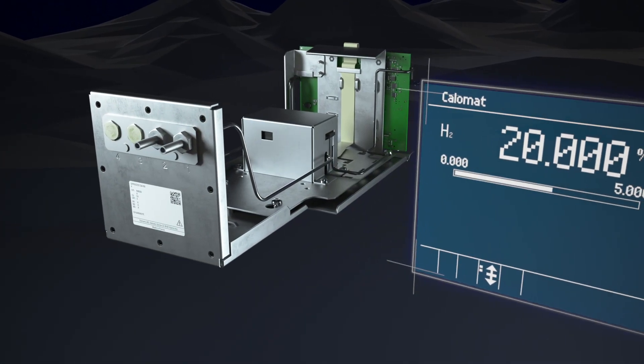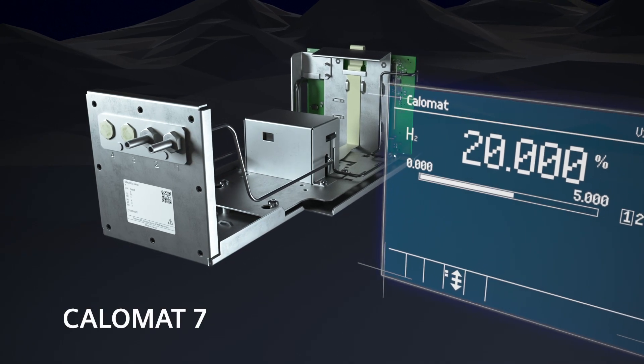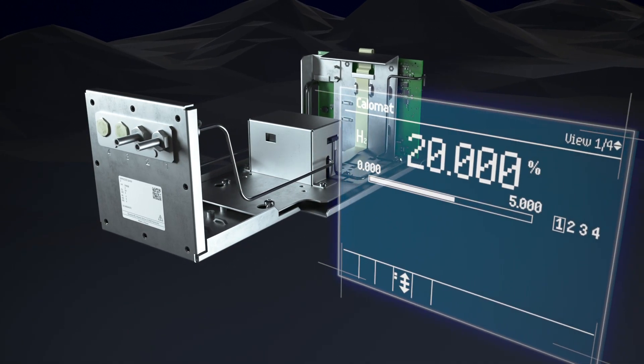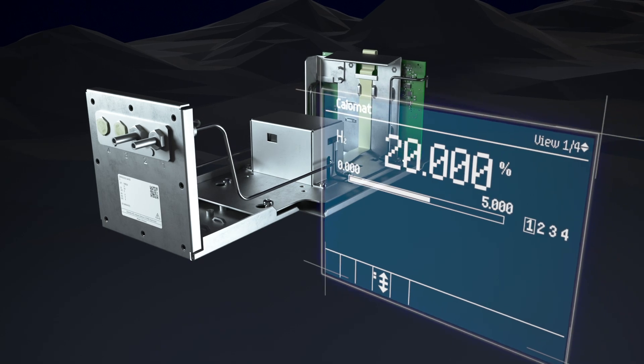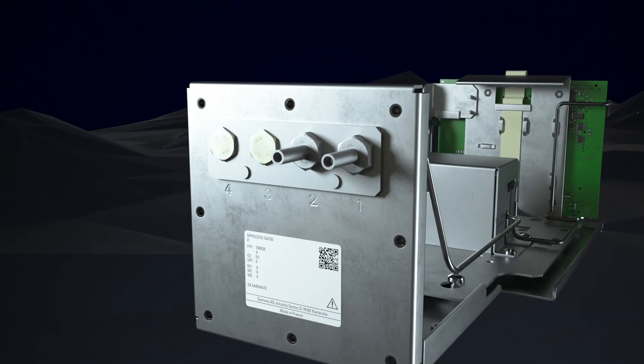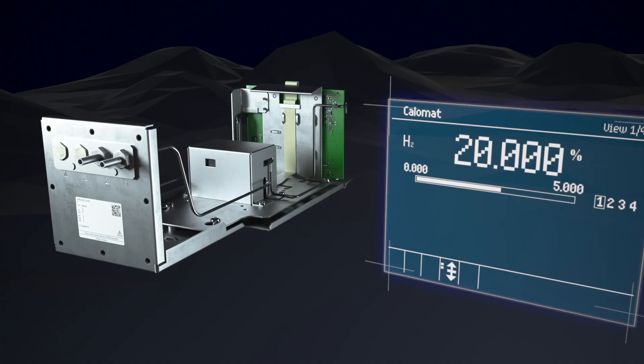The new Calomat 7, designed specifically for measuring hydrogen and helium, supplements the Siprocess GA700 platform. Like the OXYMAT and Ultramat, it can measure 11 predefined gas mixtures extremely precisely.